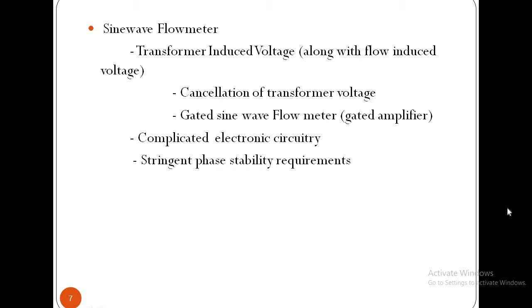In earlier versions of sine wave flow meters, this unwanted voltage was eliminated by injecting into the signal a voltage of equal strength but having an opposite phase. The artifact signal is thus cancelled and only the flow induced voltage is left behind for display.